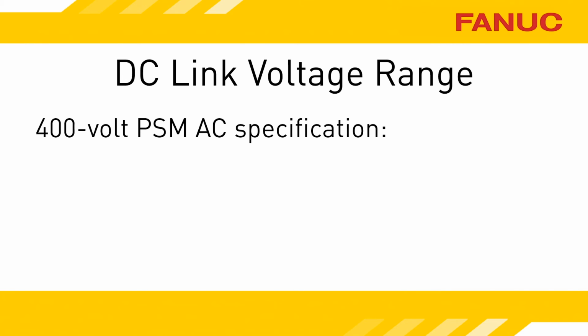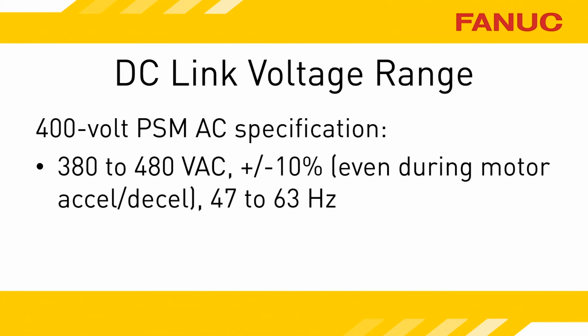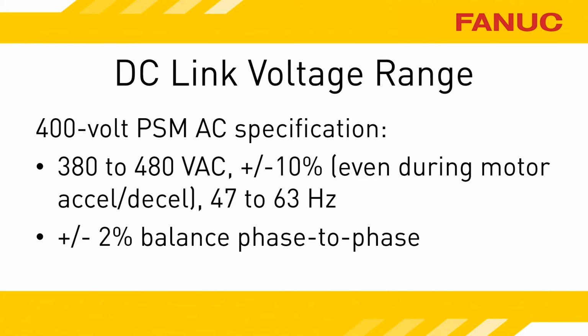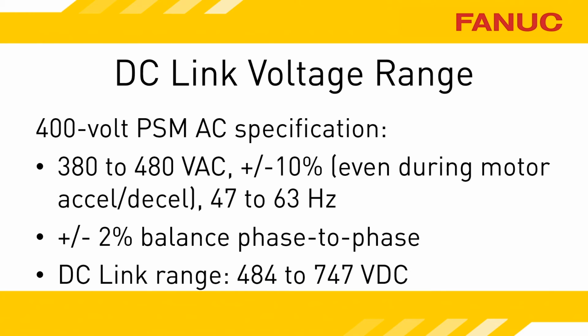For a 400 volt drive, the AC spec is 380 to 480 volts AC, no less than 342, no more than 528. The same stipulations as the 200 volt units apply. The DC link should be no less than 484 volts, or you can expect alarms.